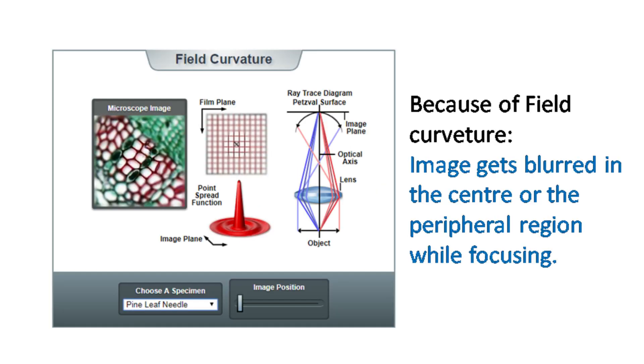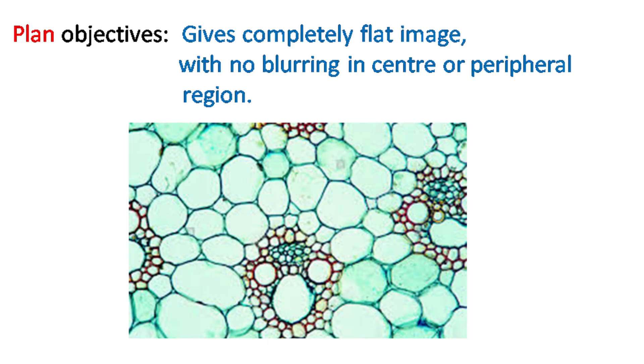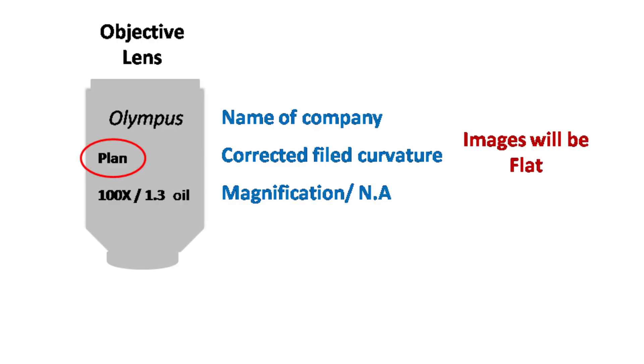Field curvature is a common aberration caused by the spherical surface of convex lens. In this phenomenon, not all parts of an image are clearly focused. While focusing in the center of an image, the peripheral region gets blurred, and while focusing in the peripheral region, the central region gets blurred. To avoid the problem of field curvature, modern objectives are designed to give a clear flat image with no blurring in center or the edge. The objectives with corrections in field curvature are called plan objectives.